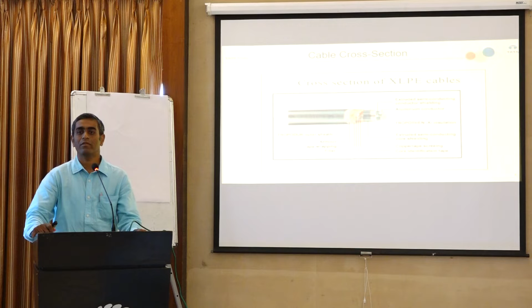While designing any project, cable is the most taken-for-granted equipment, because when we design a project, we always talk about the transformer and breakers, and we just calculate the ratings and simply decide the cable ratings. Then we prepare a cable schedule and lay the cables. But when it comes to OPEX, it is one of the most cost-consuming equipment, because whenever there is a fault, everyone rushes to the cable team or the maintenance guy to repair that fault, to bring the whole plant or whole operation back in service.